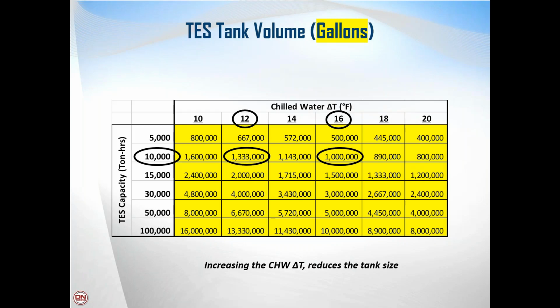So anytime engineers or owners are looking at a thermal storage tank system, it's always prudent for them to look at how they can increase the delta T of their chill water system, increase that differential between the supply and return temperatures. That will help reduce the size of the thermal storage tank that will be needed for their system.